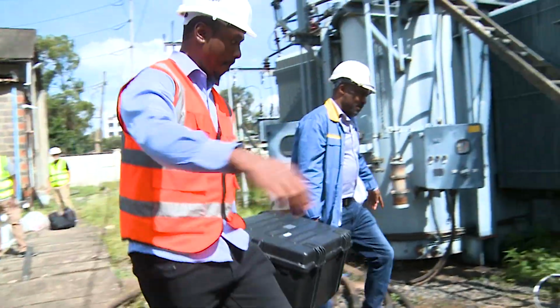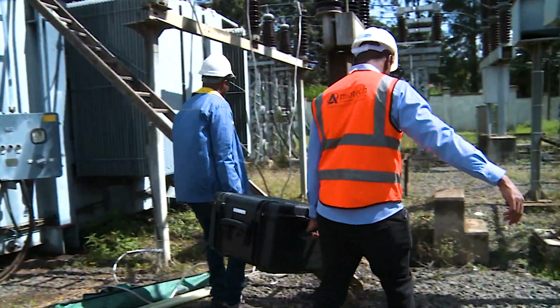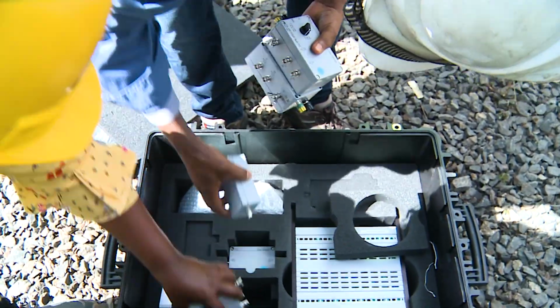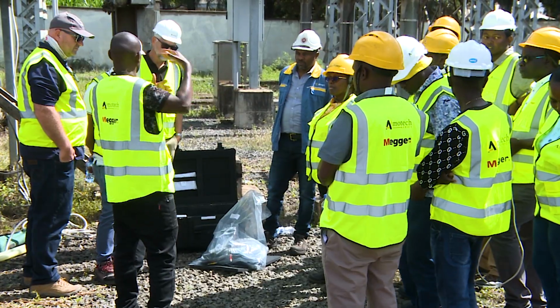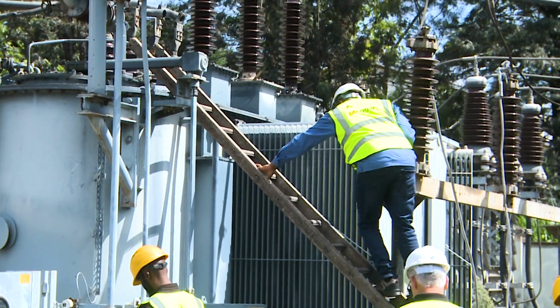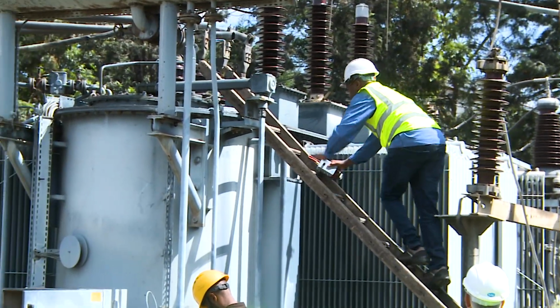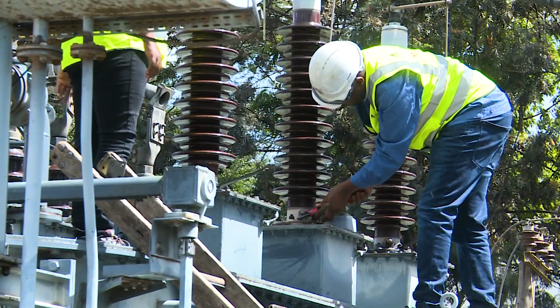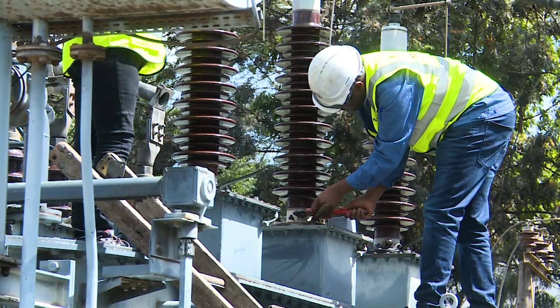We have supplied the ICM system, which is a portable partial discharge test equipment, and today we are just having a practical session. With this partial discharge test, the Kenya Power team can detect early the deterioration of the insulation and see the PD signals. Once they detect the partial discharge at the early stages, they can react to it faster and save the asset.